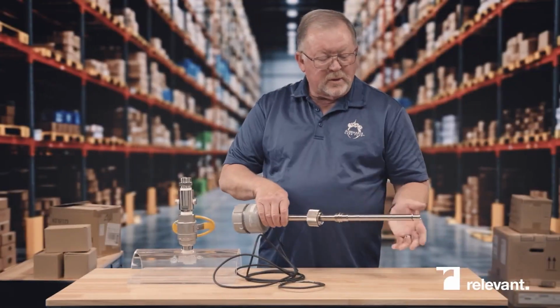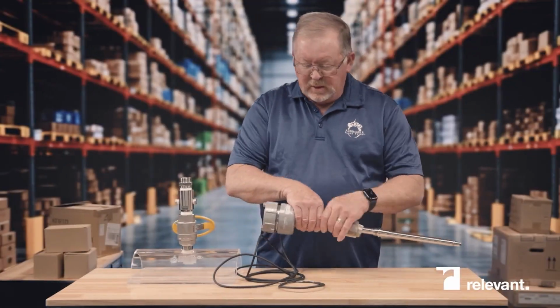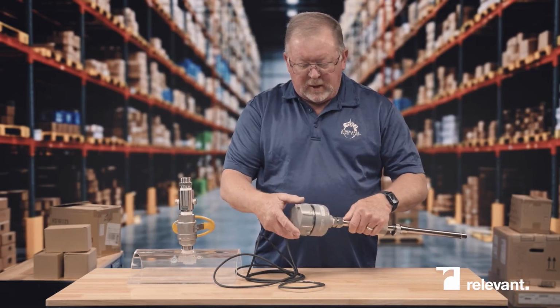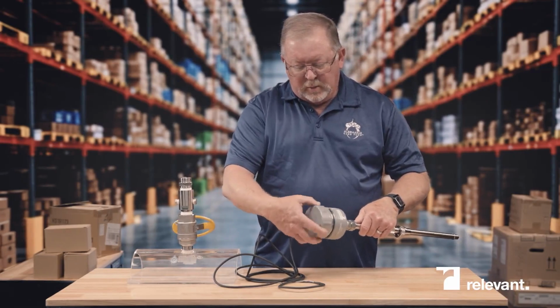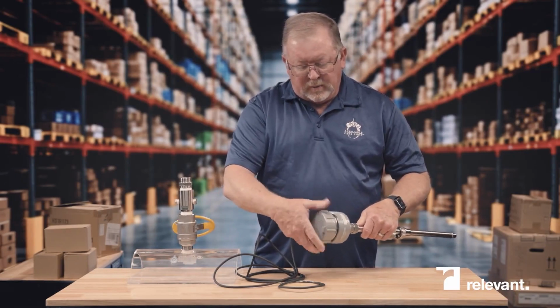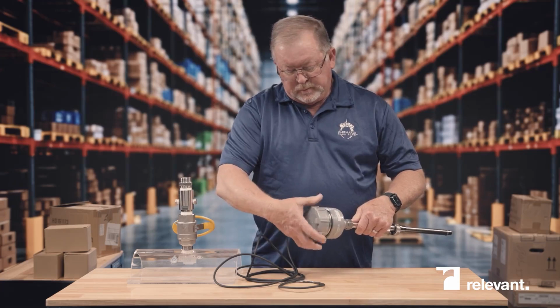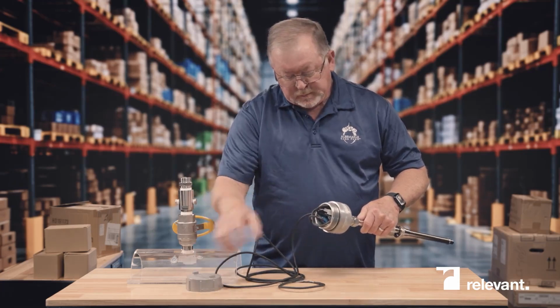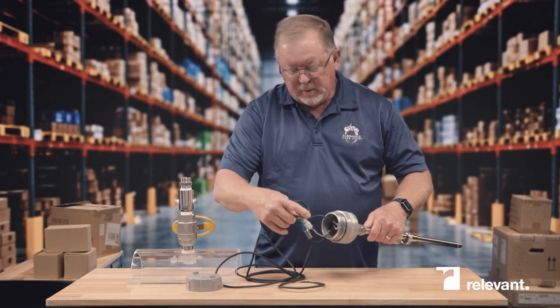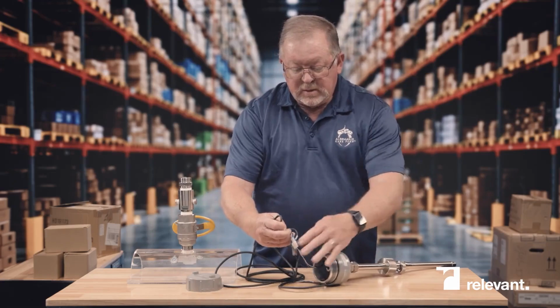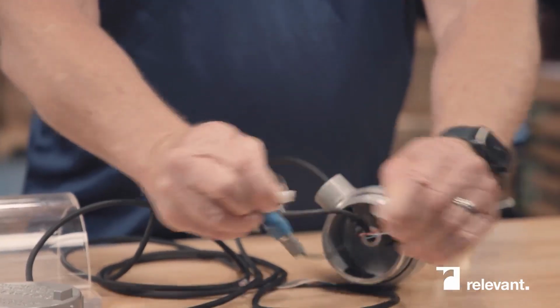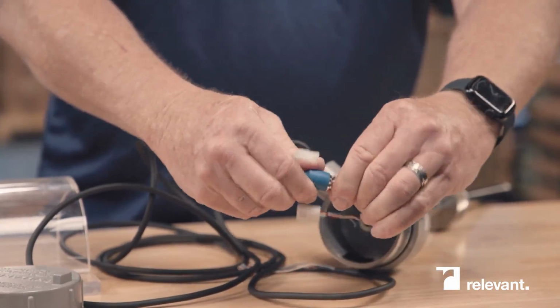We have now determined that the electrode needs to be replaced. So in this case, once you have the unit out in hand, you will remove the back cover of the J-box. Fine threads, of course. Inside you will find the extension cable with a BNC and a Molex. You will simply remove those.